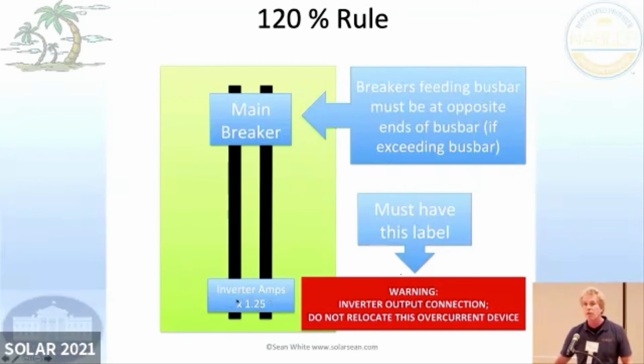A 16 amp inverter is a 3.8 kilowatt inverter, and a 3.8 kilowatt inverter is way more popular than a 4 kilowatt inverter because they make it to fit on a 20 amp breaker. And that's for 240 volts too. So when I say 3.8 kilowatts, that would be 240 times 16 amps is 3840 watts, 3.8 kilowatts. And then it needs to have that sticker at the opposite end of the bus bar.